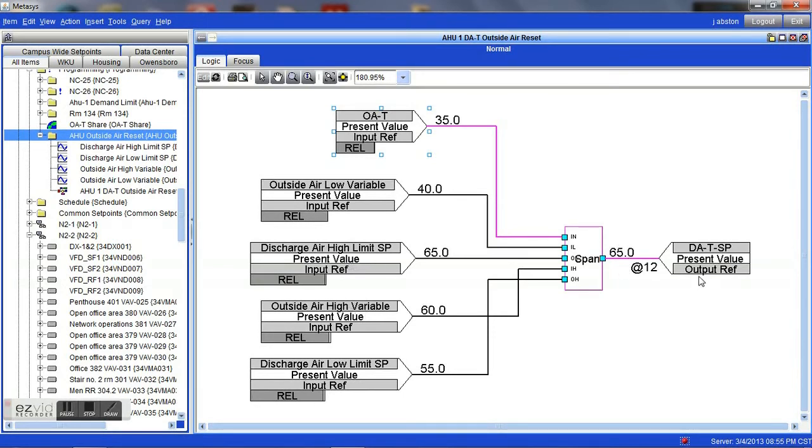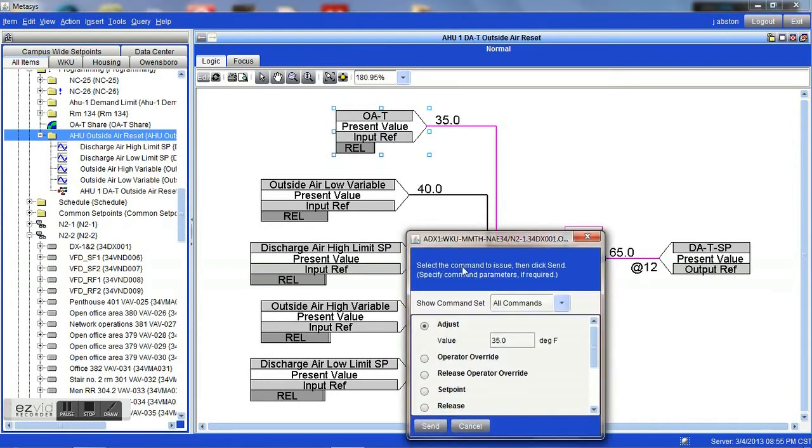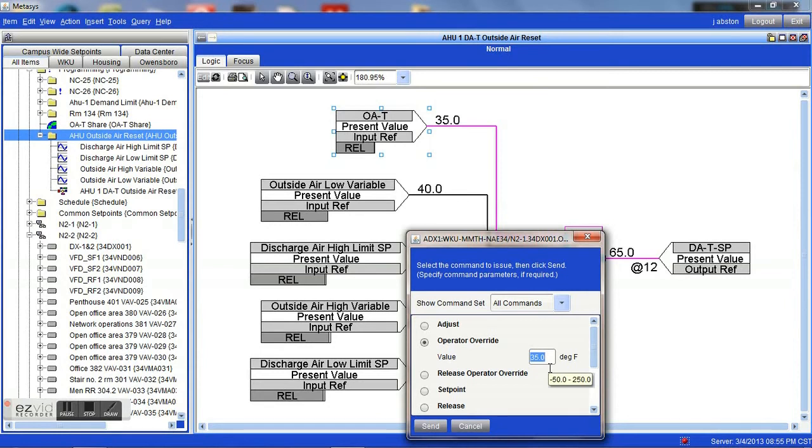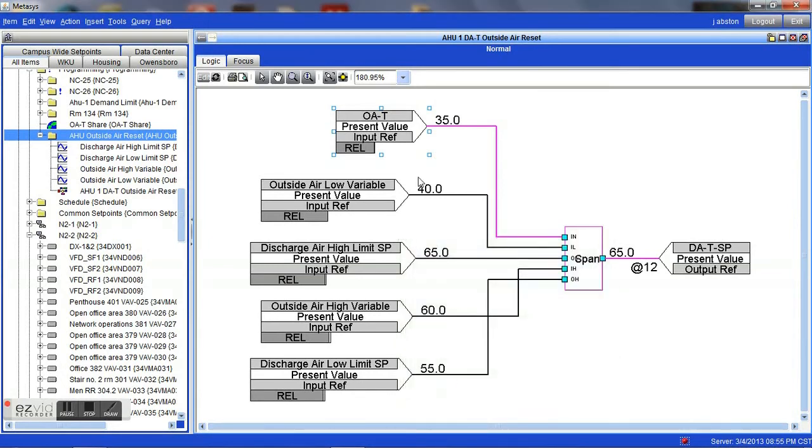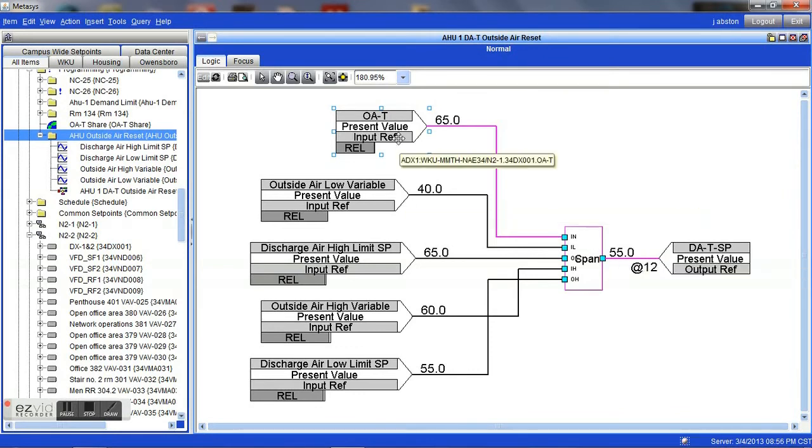Now then, just the opposite will be true if we were to go the other way. For example, if we were to command this and override it to a value above our outside air temp variable, if we say go to 65 degrees instead of 35, you will see that based upon the logic, the value will change as well. You can see that it immediately changed and went to a 55 degree temperature on the discharge set point.